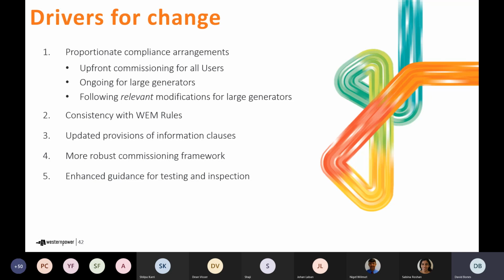So the approach we've landed on is for all users, there needs to be appropriate upfront commissioning of their facilities. And as part of that commissioning will include demonstration of being able to meet the relevant technical performance requirements. For large generators, there's a need to implement an ongoing compliance monitoring program, very similar in the way that's implemented to what's described in the WEM rules for large transmission connected market generators. And there's a need to reconsider that compliance assessment following any relevant modifications. So we're achieving through that the consistency with the WEM rules.